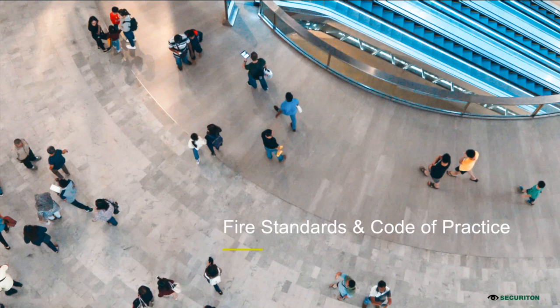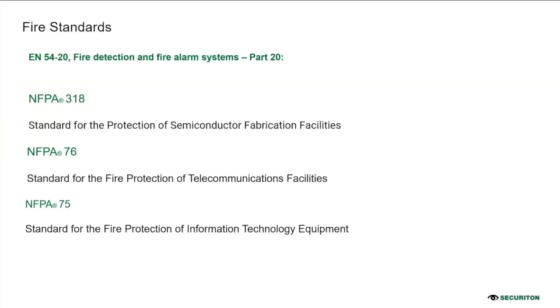Now, if you look into clean rooms, there are fire standards and codes of practice used to design fire systems. Not only fire systems, there are also classifications on how you design, fabricate, as well as maintain the sites from fire. So the standards we're going to look into today, just a rough idea of what standards are used in European markets. Obviously, we will be using EN 54-20, or European Norm Part 20, for ASD. And if you look around the world, the American standards have NFPA 318, which is the standard for protection of semiconductor fabrication, that mainly talks about protecting sites from fire.